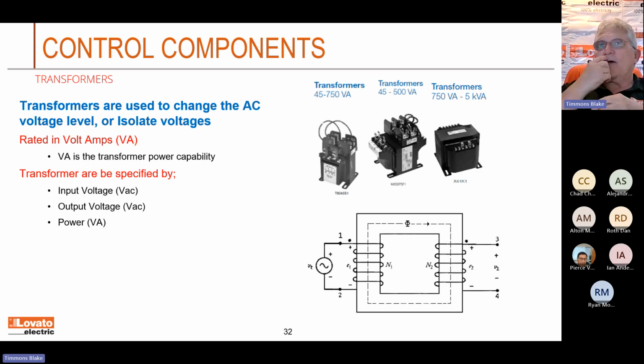Now you're not going to get the power. The formula was always power in equals power out minus some heat loss. But that's all a transformer is. It's just a reducer. You reduce it up, you reduce it down. Works both ways. And usually you're sizing those things by volt amps. Volts times amps is usually power, right, without any reactance. But that's how you size those things.